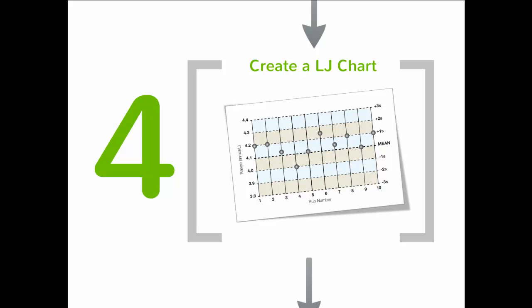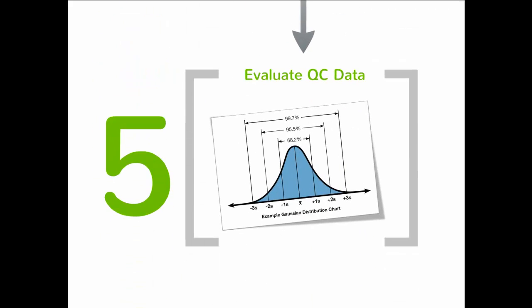Finally, evaluate the QC data. When an analytical process is in control, the QC data will fall in a distribution with approximately 99.7% of the results falling within the ±3s limits. QC results that are outside the ±3s limits are generally considered out of control and the run should be rejected. QC data greater than 2s but within the ±3s limit does not necessarily indicate that the run must be rejected, as approximately 4% of the valid data points will fall between 2s and 3s.